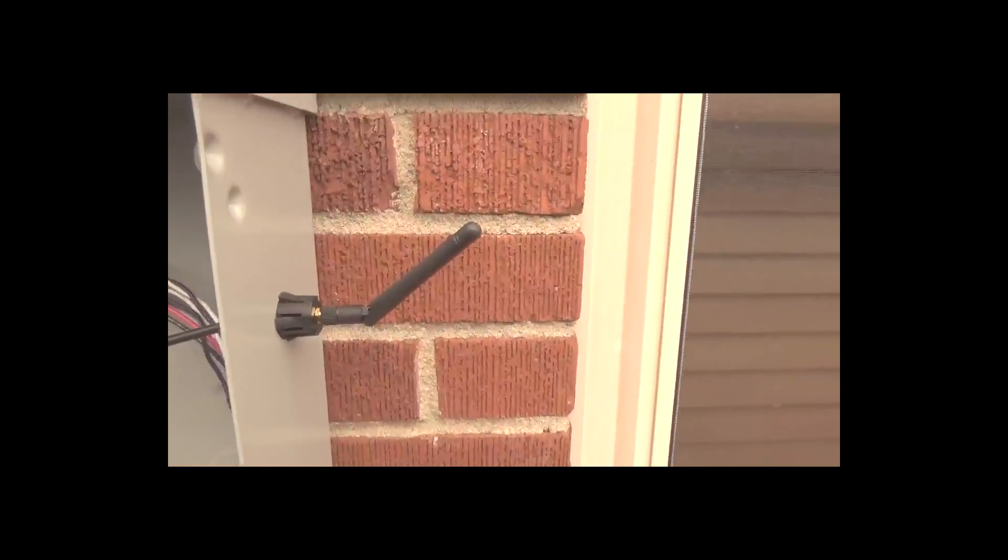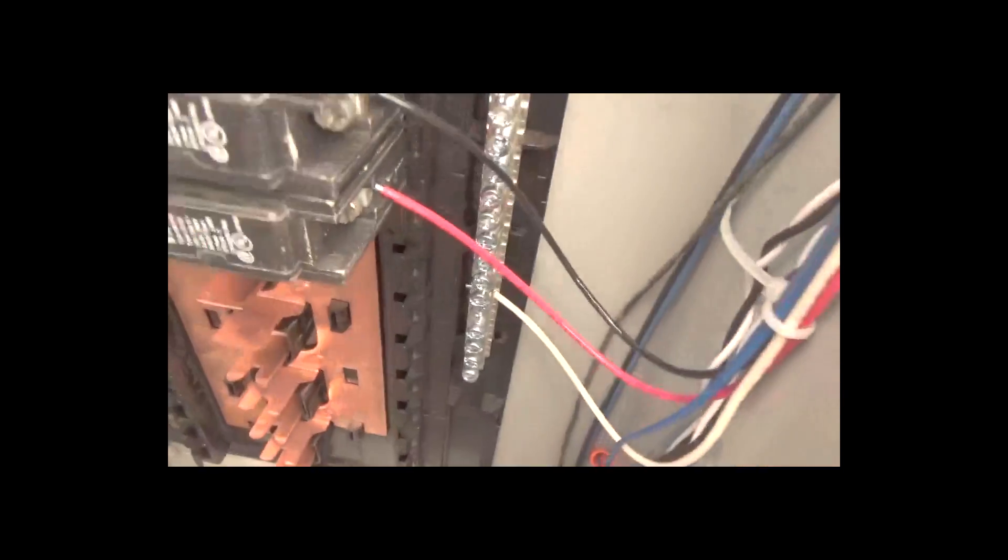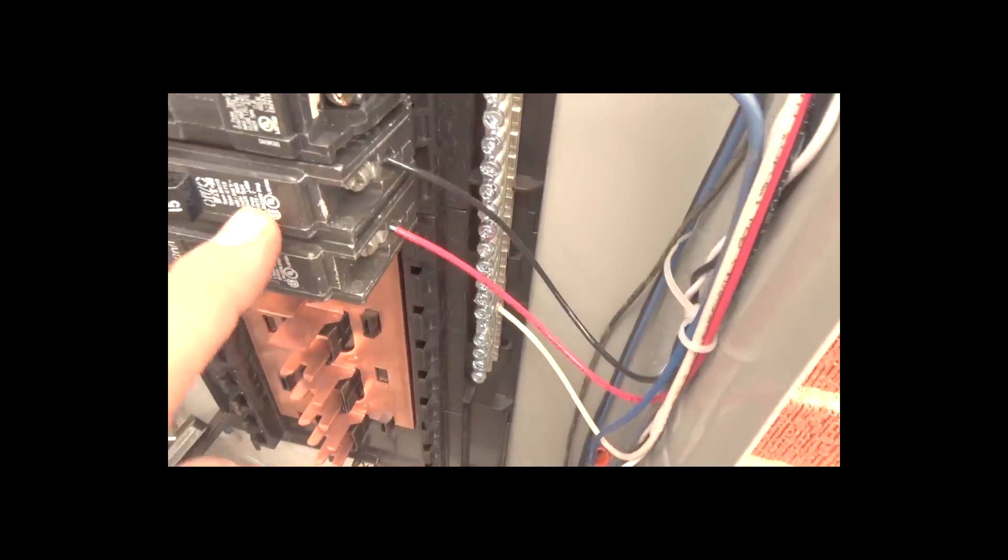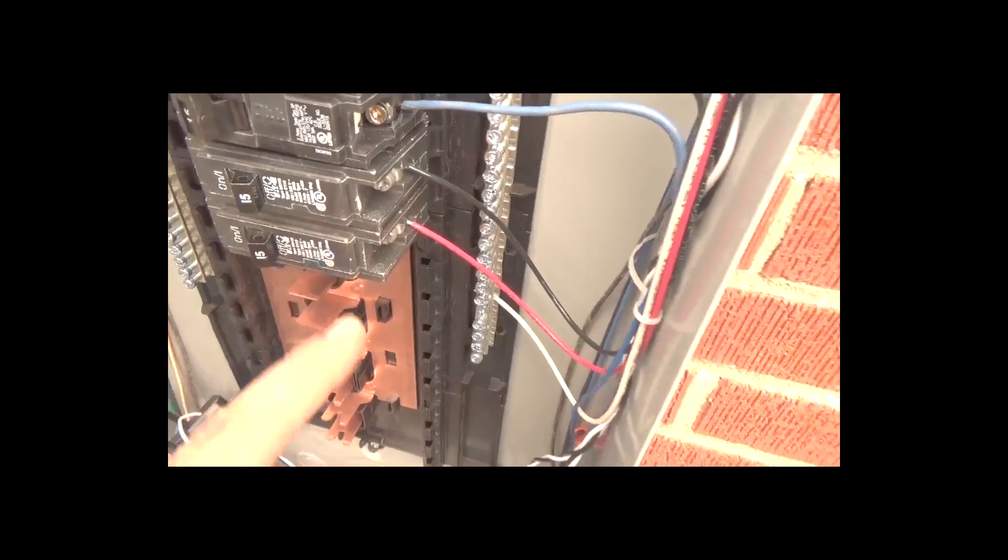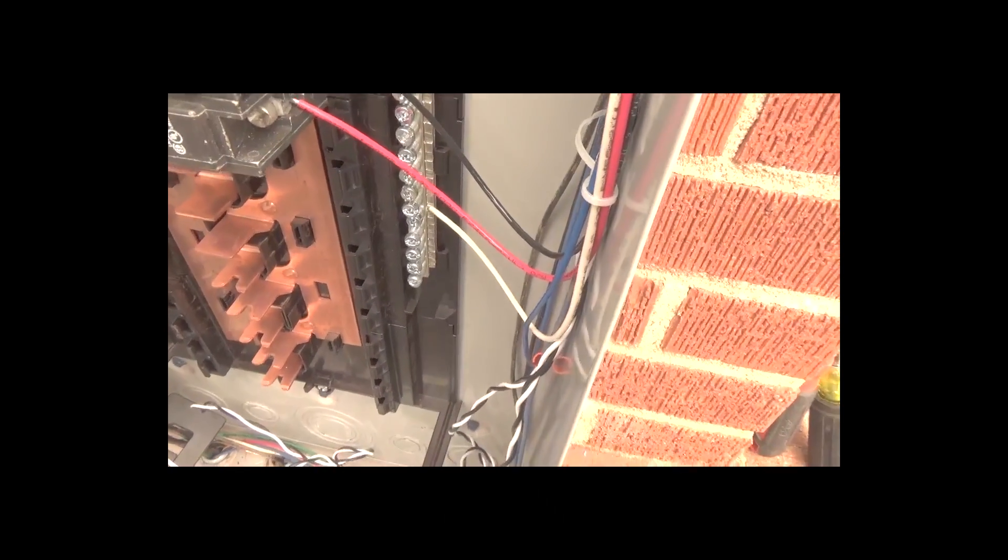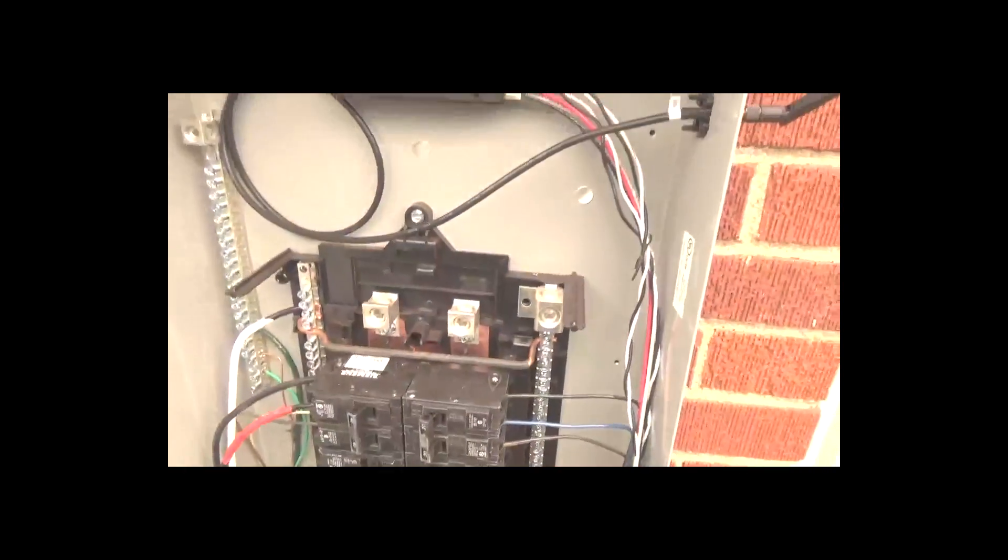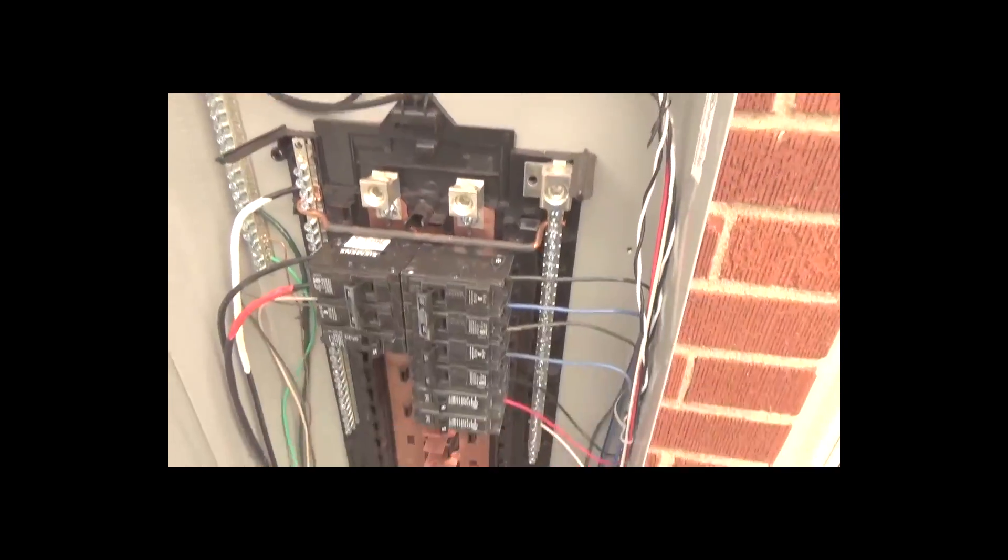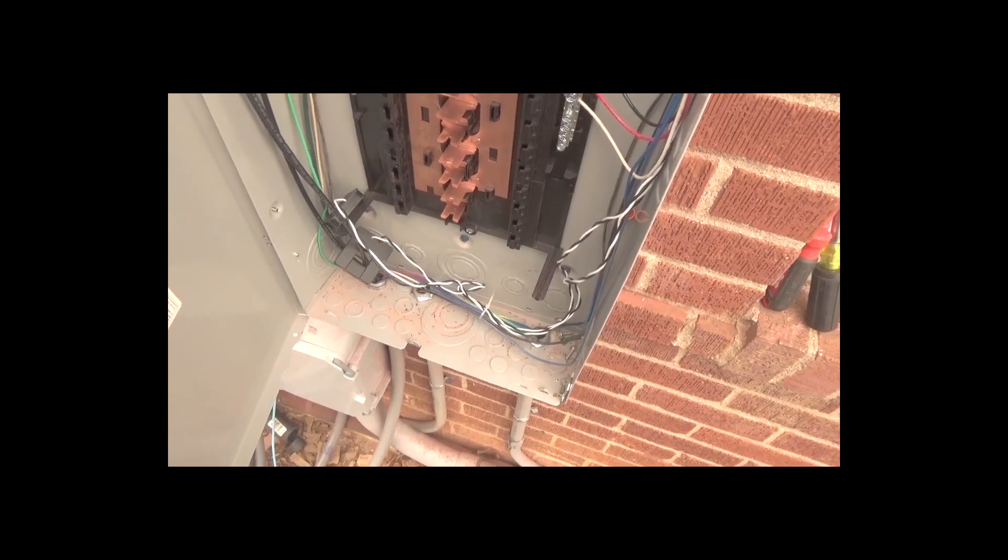Okay, got the Nurio in, the antenna coming out the side of the panel box, got the wires rounded. You got to have two wires for the voltage calculations, one wire goes to the neutral bus bar, and then the two current transformers are placed in here with the labels facing the source of power which is opposite away from me. That's it, so we're going to fire this thing up and turn this chiller back on, and then we got to configure it for the web.